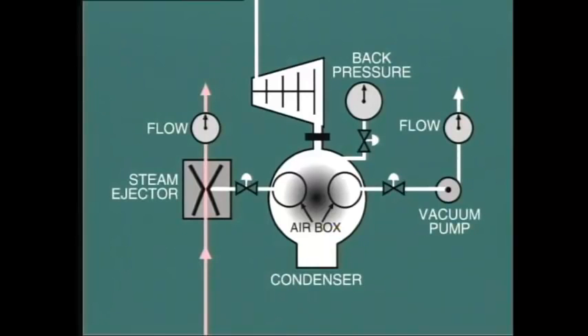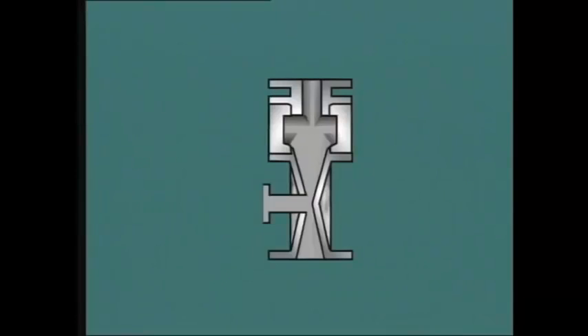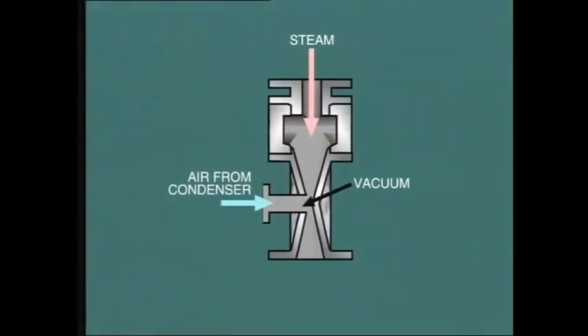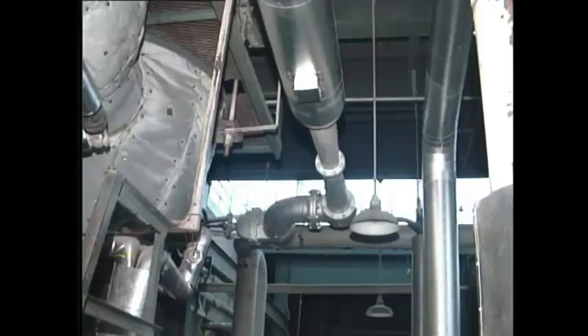Let's see how the steam ejector works. This functions on the principle of the Venturi nozzle, like this. When high-velocity steam passes through this nozzle, it creates a vacuum at this convergent point. This is the point which is connected to the air box in the condenser. The air enters the nozzle and is mixed with the steam passing through. On a startup ejector, also known as a hogging ejector, this mixture is discharged to atmosphere.